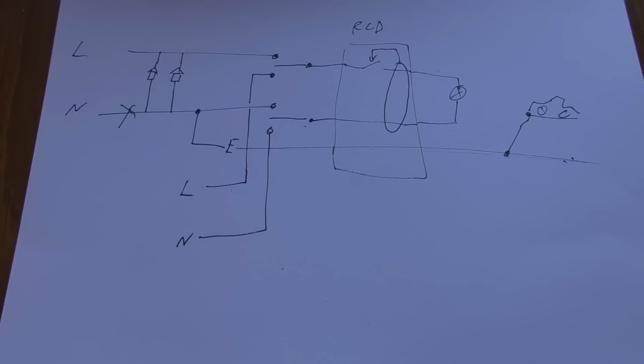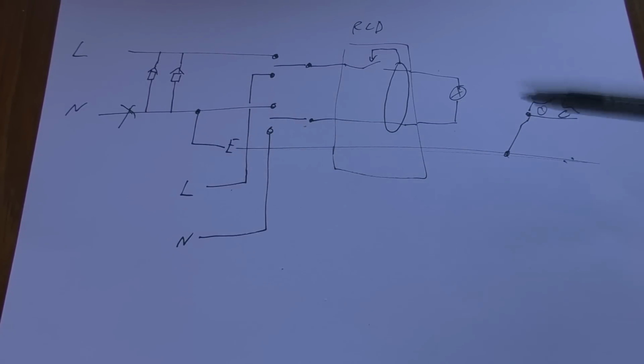The only potential safety issue is that in the case of a fault, an RCD won't trip. But because the source is floating, the consequences of that are significantly reduced. Also, the fact that it's only going to be running on this backup for very short periods means statistically the chances of that being an issue are greatly reduced. So it's not something that's a particular concern, I think.